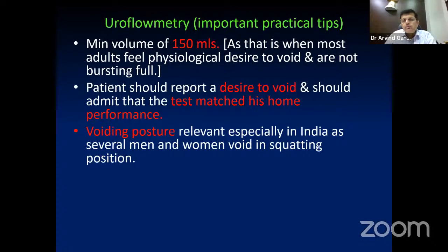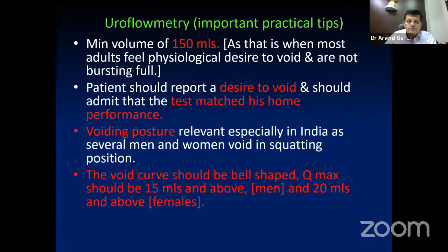One important thing that you always have to consider is the voiding posture. In India, most of the women and many of the men will void in a squatting position. So you have to make a provision that if they have got this habit, the patient should be able to void in the same squatting position, even in the uroflowmetry machine.